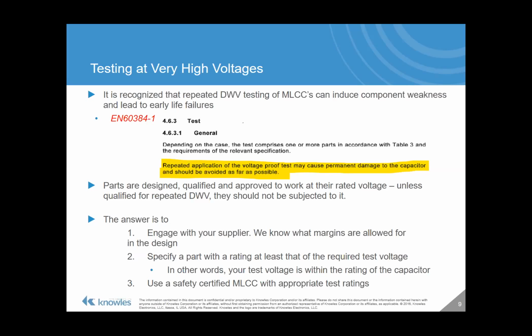So if you are looking at testing at 4000 volts DC, you need to be looking for a part that has a rated voltage of 4000 volts DC. It may sound as if you are vastly overrating the part, but you do not want to be risking the lifetime of your vehicle. The answer is engage with us, engage with your supplier. We know what margins we're allowing for in the design. If we don't think the part you're designing in will be suitable, we will tell you and we will suggest alternatives. Specify a part with a rating at least the required test voltage. So if you want a 4000 volt DWV, specify a 4000 volt rated capacitor. The slight exception is safety certified. That generally has appropriate test ratings, and I'll show you some of the ratings about the safety certified parts a little later on in the presentation.